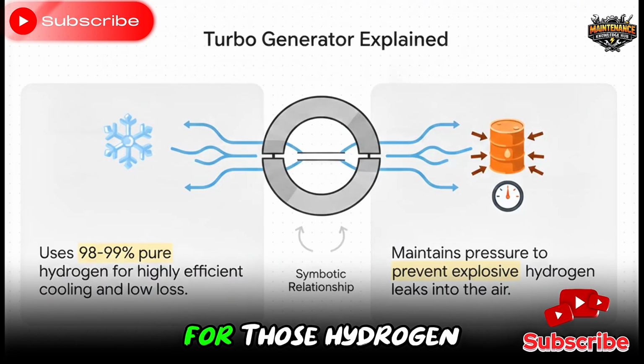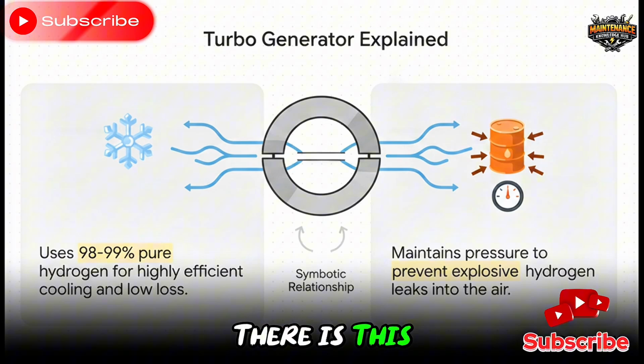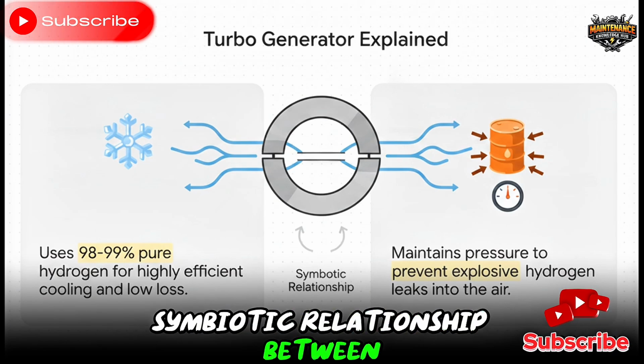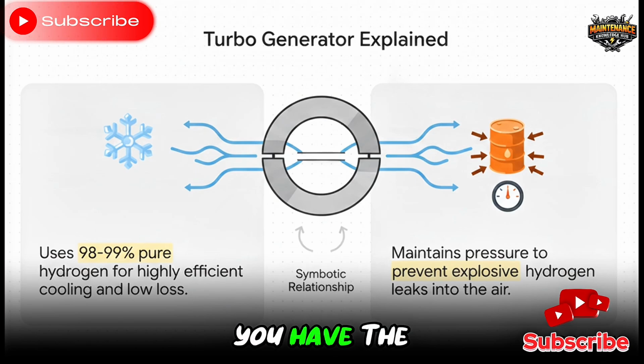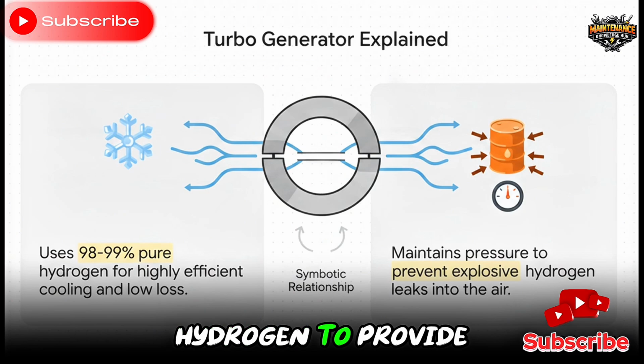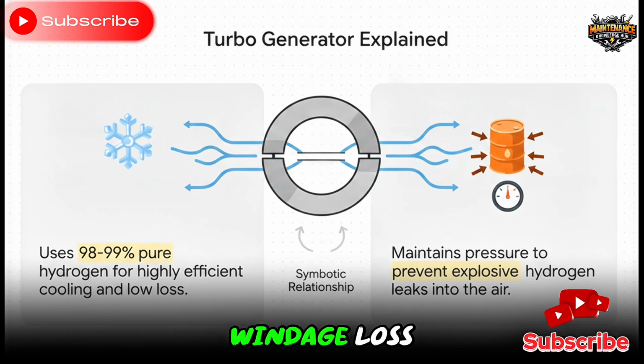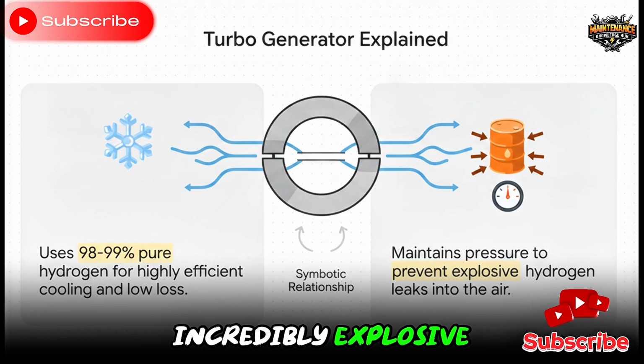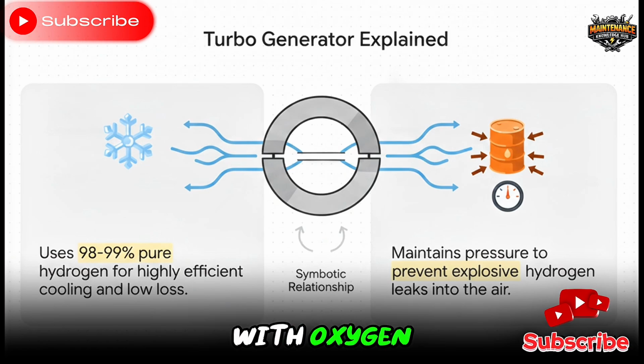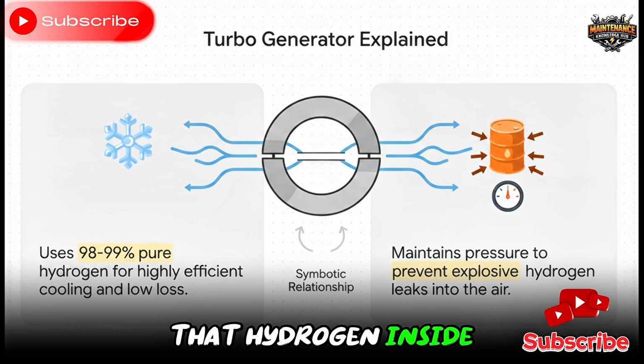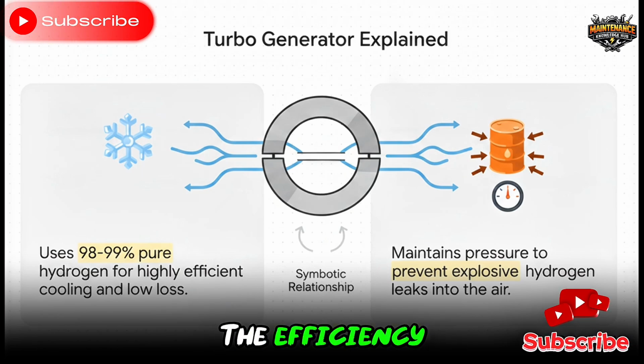Absolutely wild. For those hydrogen-cooled units we just mentioned, there is this fascinating symbiotic relationship between two main systems. On one hand, you have the hydrogen cooling system itself, utilizing 98 to 99% pure hydrogen to provide highly efficient cooling with very low windage loss. But hydrogen is incredibly explosive if it leaks out and mixes with oxygen. Enter the seal oil system. Its entire job in life is to maintain a precise pressure difference, pushing oil against the seals to safely trap that hydrogen inside the casing. So the cooling system gives you the efficiency, while the seal oil system guarantees your safety.